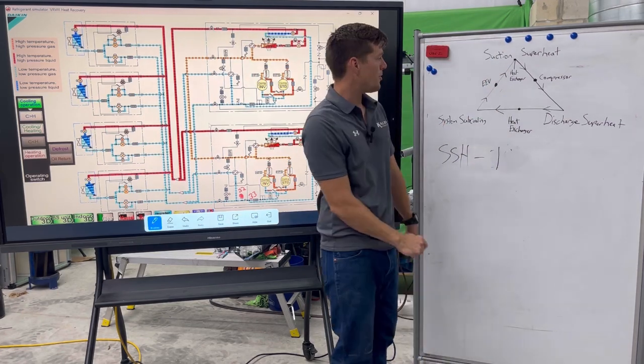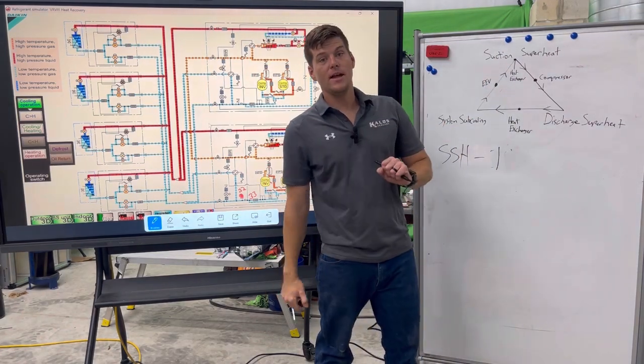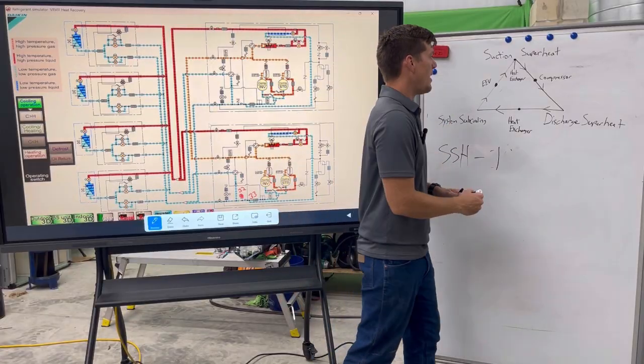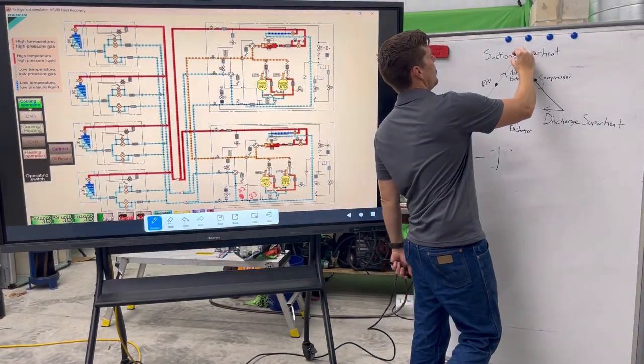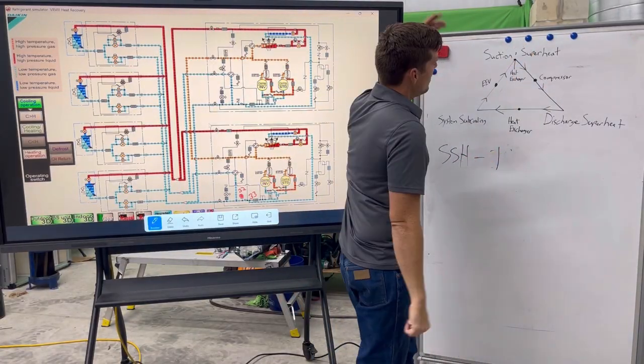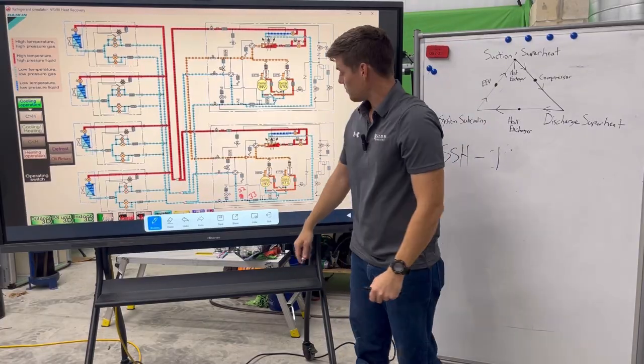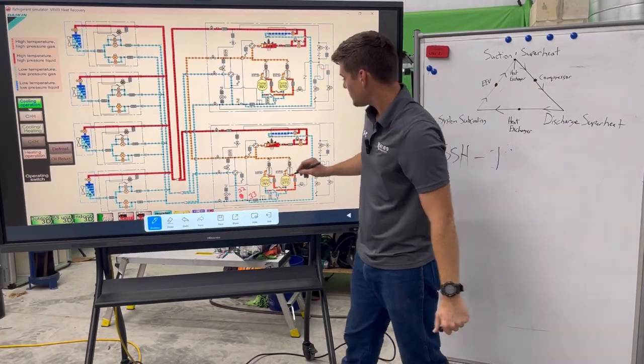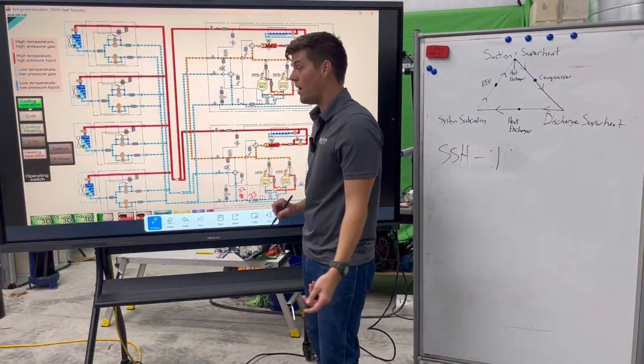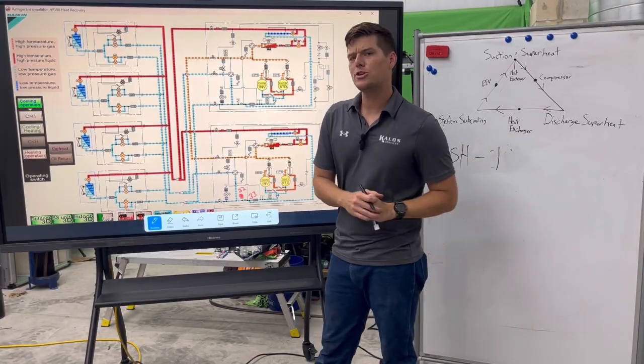Suction superheat, 1 degree. Okay, we got 1 degree at the top. That tells me that I've got liquid coming back to my compressor. I'll even put a nice little 1 here at the top of my chart. Now I'm going into my compressor. What's going to come out the other side? Well, coming out the other side, we have what? We have a high pressure sensor. What does that high pressure sensor tell us?